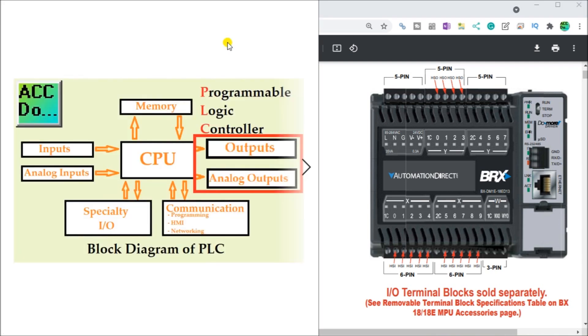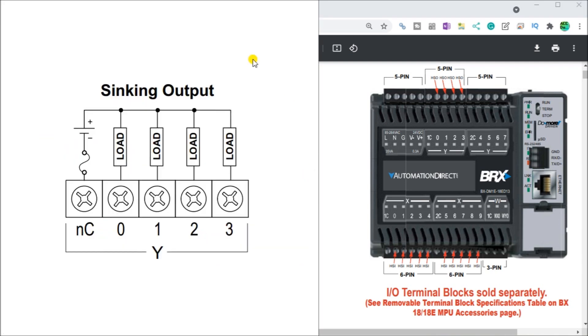Let's first look at our discrete digital outputs. As mentioned, they're either on or off — think of these as switches that control the load. If the PLC output is off, the switch is open and the electrical circuit is not complete, so the load is not energized. If the PLC output is on, the switch is closed and the electrical circuit is complete, so the load is energized. It is important to look at the switching capacity to determine that the load will not exceed the limit.